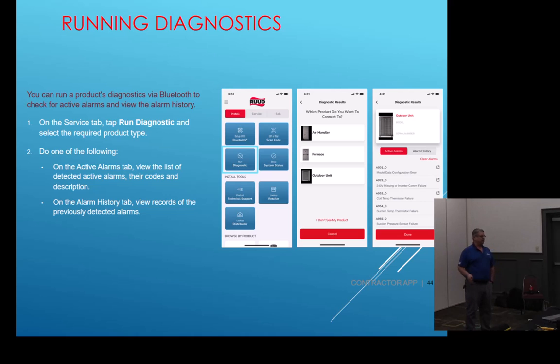The O would be for what? Outdoor unit, right? An A would be for what, guys? Air handler. F would be for a furnace. That's very important. I've had guys call me and say, Mike, I've had the thermistor failure. I've changed it 3 times. It's still giving me the same thermistor failure. What code do you have? I have an A953O. Where'd you change the thermistor? On the air handler. Wrong piece of equipment. So we need to know, because we've got thermistors inside and outside. So we need to know that last letter designation so we know what piece of equipment we're working on. Okay? It's very important.